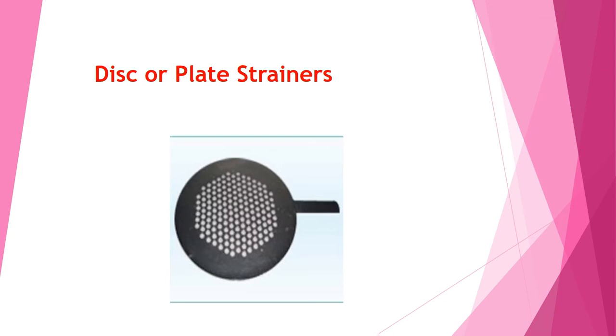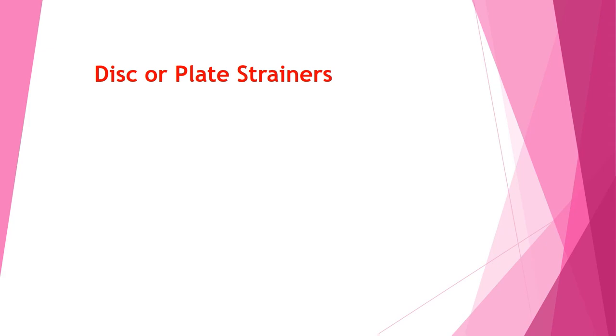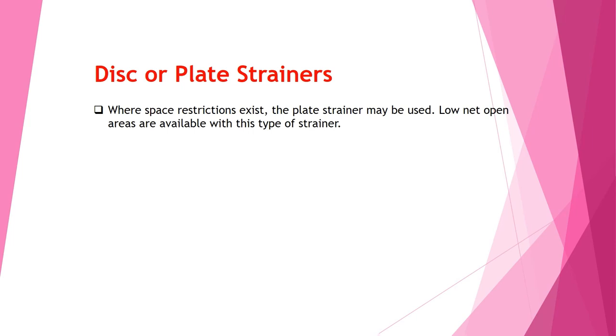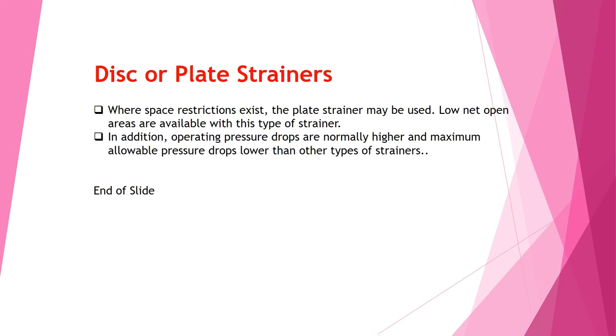The third type is the disc or plate strainers. Where a space restriction exists, the plate strainer may be used. Low net open areas are available with this type of strainer. In addition, operating pressure drops are normally higher and maximum allowable pressure drops lower than other types of strainer.